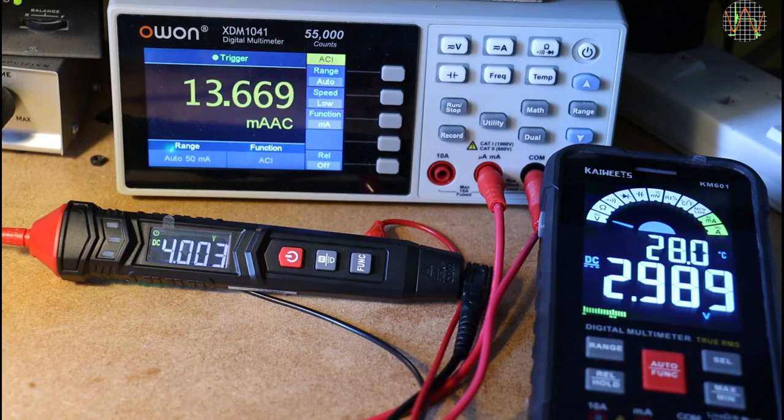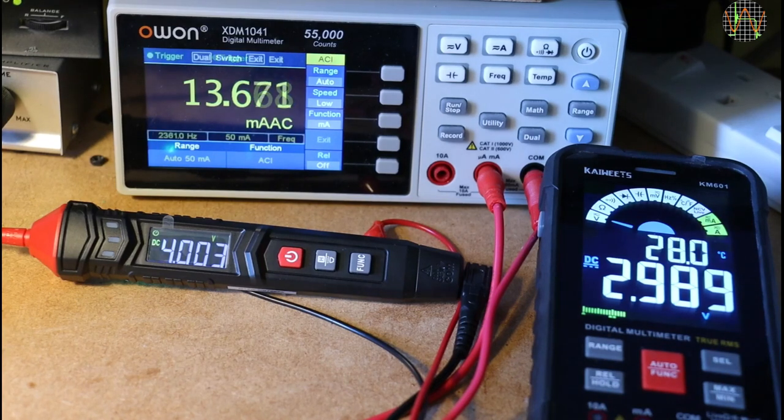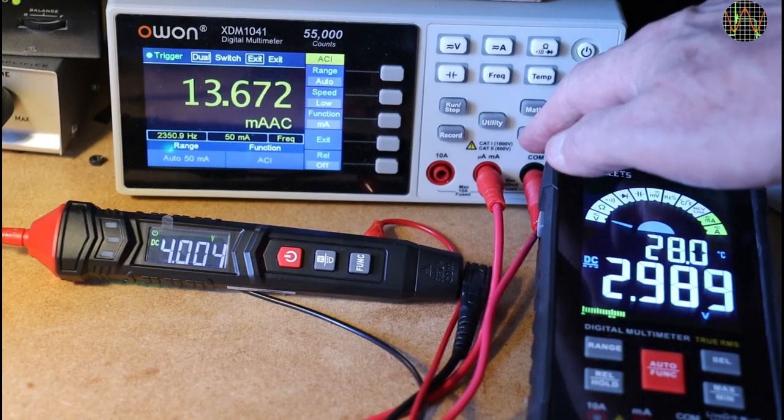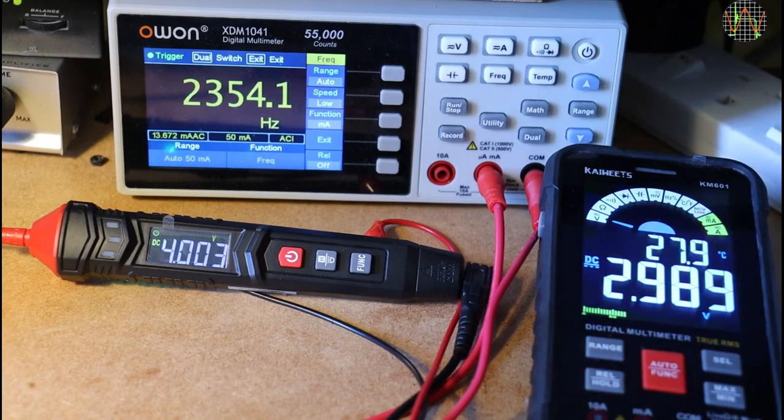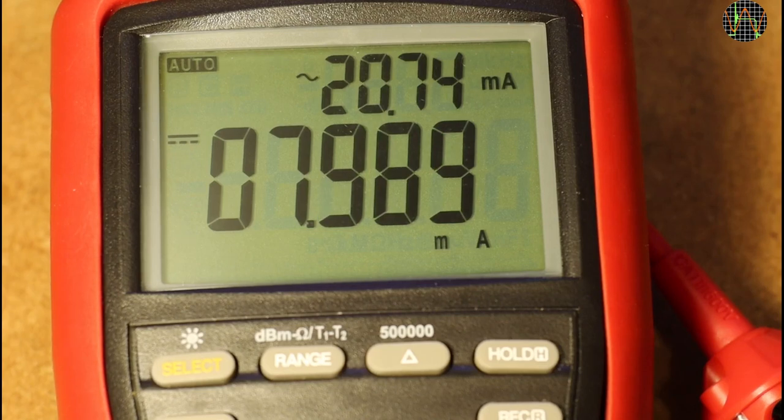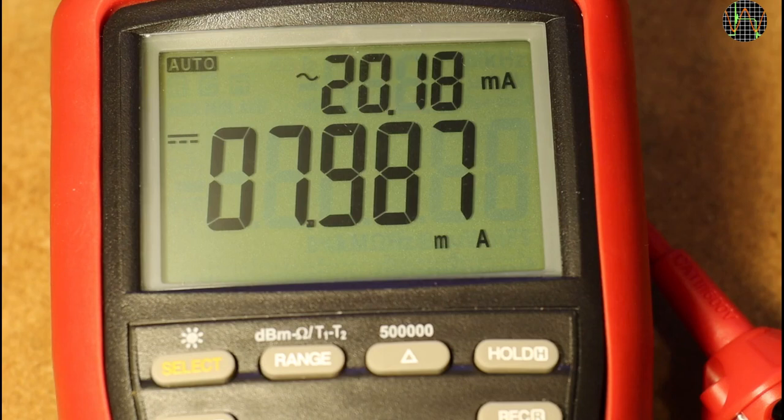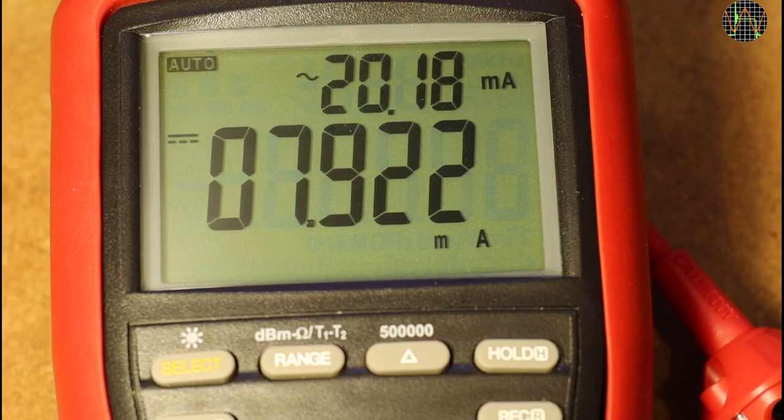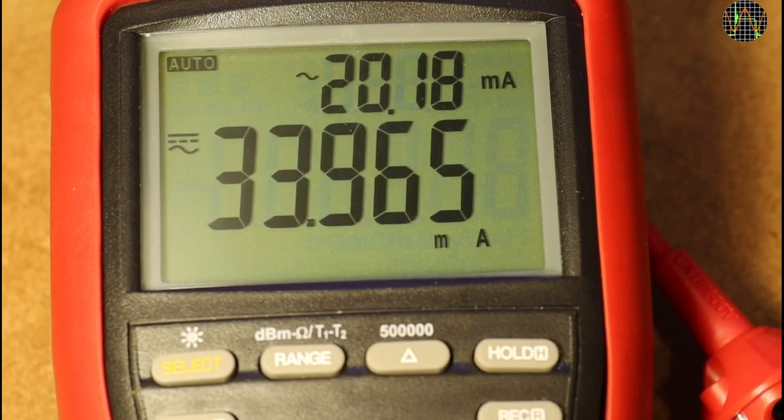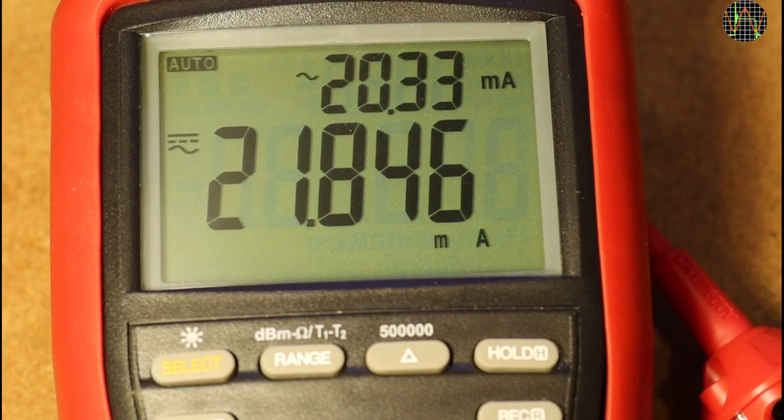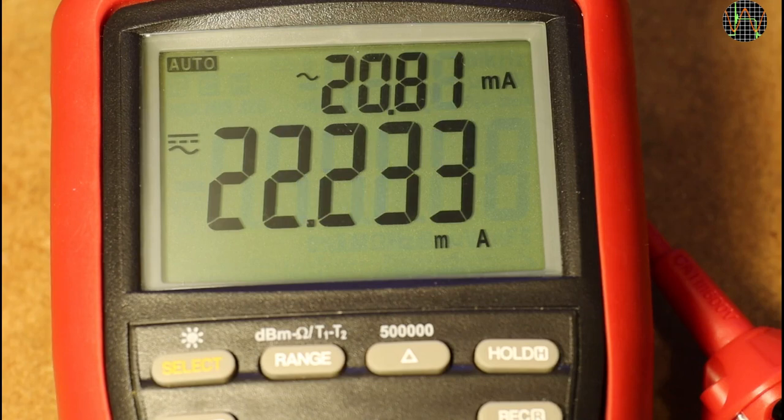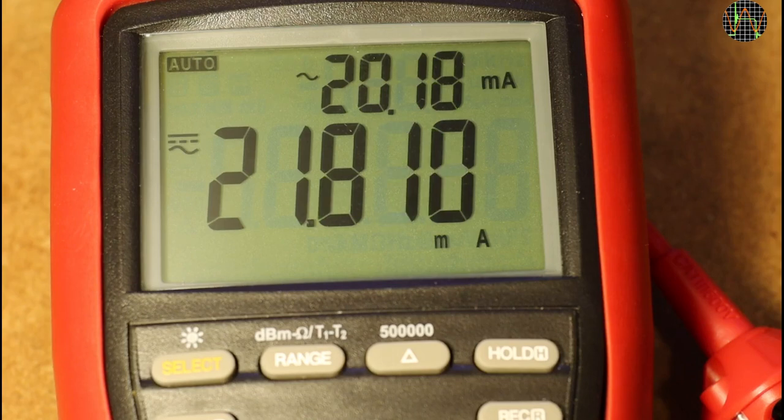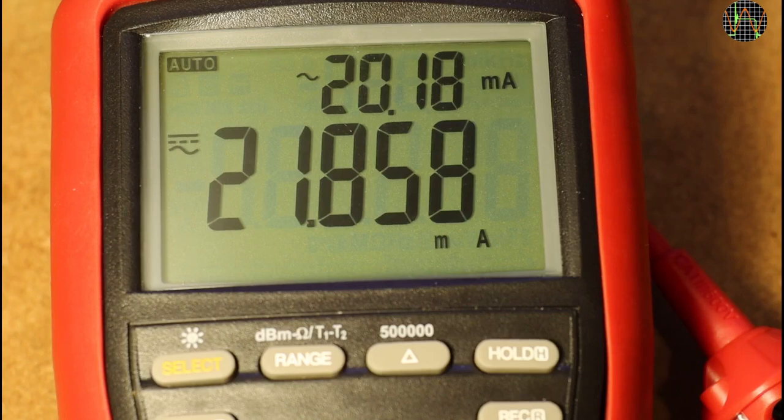Wow, more than 13.5mA AC current on top of the 7.7mA DC. That makes 15.7mA AC plus DC total using vector addition. The frequency of the converter is apparently about 2.3kHz. And that frequency meant that the Owon with its 1kHz AC bandwidth, same as the ST120 by the way, isn't the meter that can accurately measure that. Here is the same measurement with the Brymen BM869s. DC current on the bottom, AC current on the top. It is more than 20mA AC current and AC plus DC is about 22mA. I do admit I only recognized that error when I was editing the video when I had to repeat the measurement with a Brymen. I left it in because it shows how important it is to know and remember the limits of your meter.